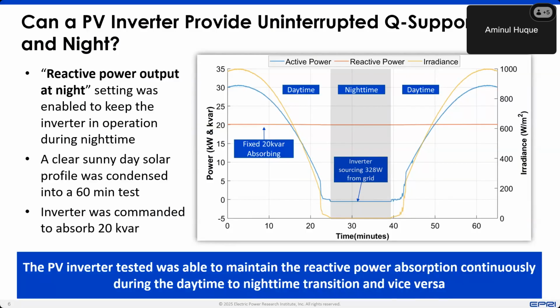They stay off or in sleep mode the whole night. In the morning, when irradiance goes up or DC voltage goes above a threshold, it wakes up and starts generating power. But if we want this plant or inverter to be available to provide reactive power, then we have to figure out whether the capability is offered by the inverter and then how to activate this capability.